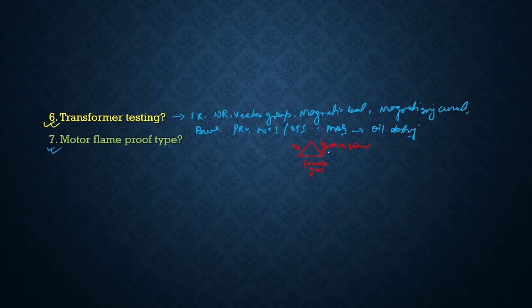So if you have an ignition source like motors and all these equipments, the sparks act like an ignition source to get fire. Oxygen is already present in the atmosphere, you will have a flammable gas already, vapor mixtures in the oil and gas industry. So these motors, these electrical equipments act like an ignition source. It will complete the fire triangle. There may be fire hazards. Because of this, they use flame proof equipments.